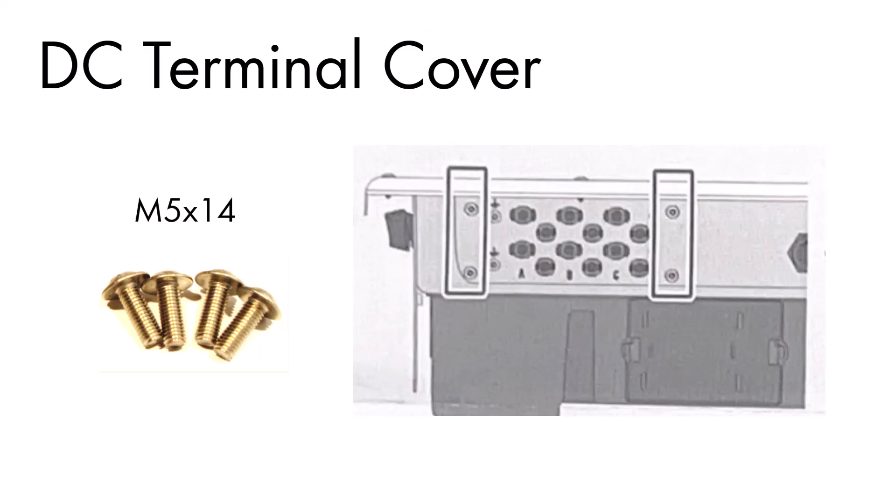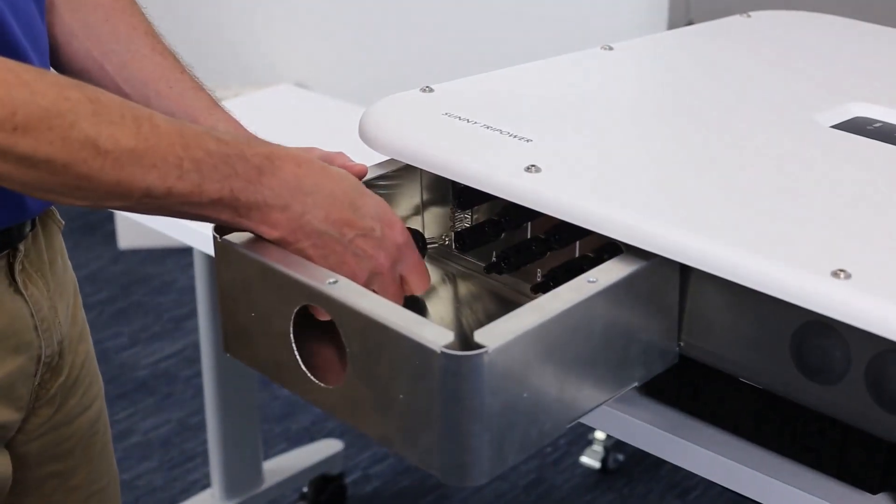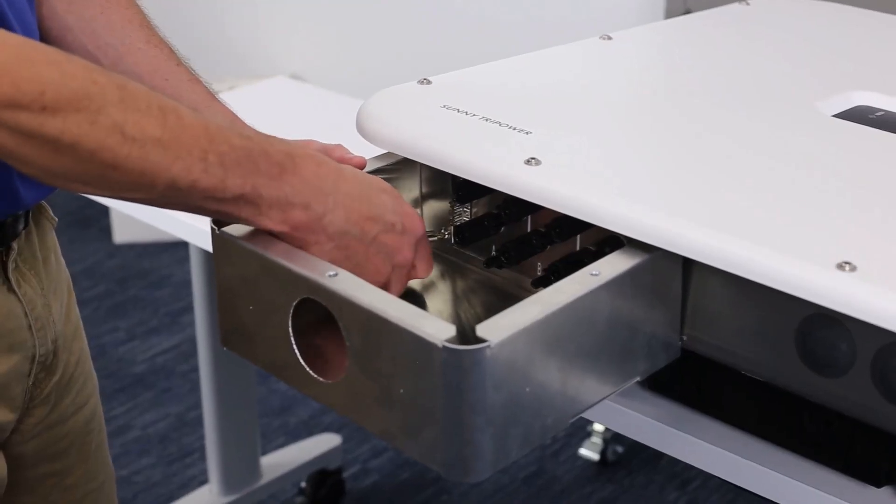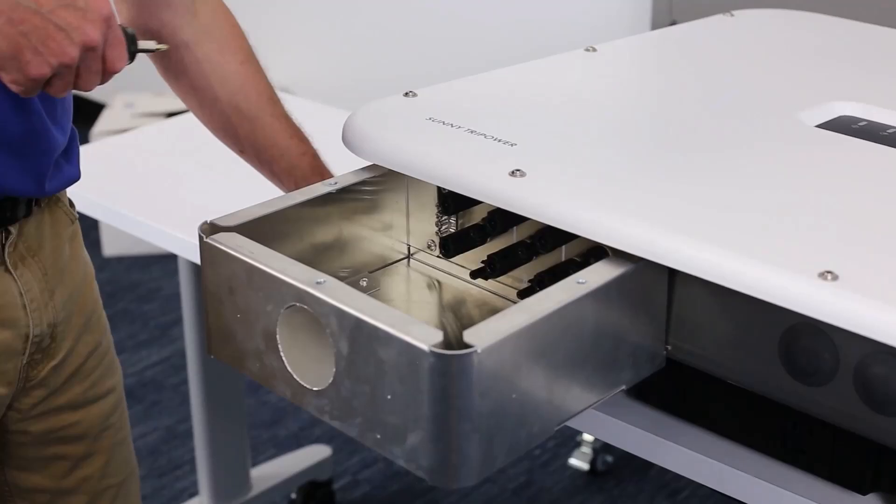The four M5 x 14 screws are used to attach the DC terminal cover to the body of the inverter, while the three M6 x 20 screws are used to secure the lid. With a torque spec of 35 inch pounds, attach the DC terminal cover securely using the four M5 x 14 screws.